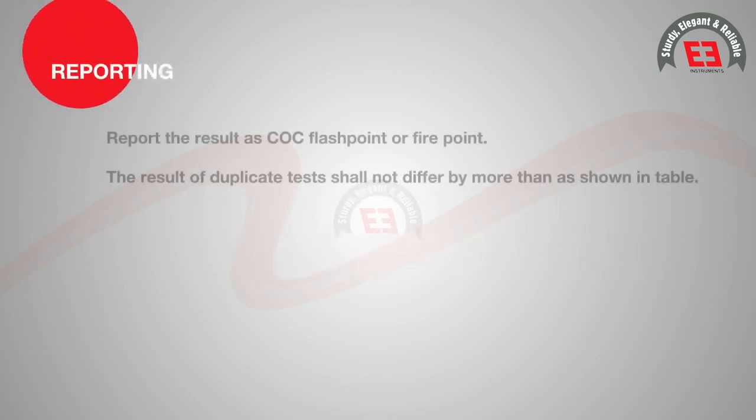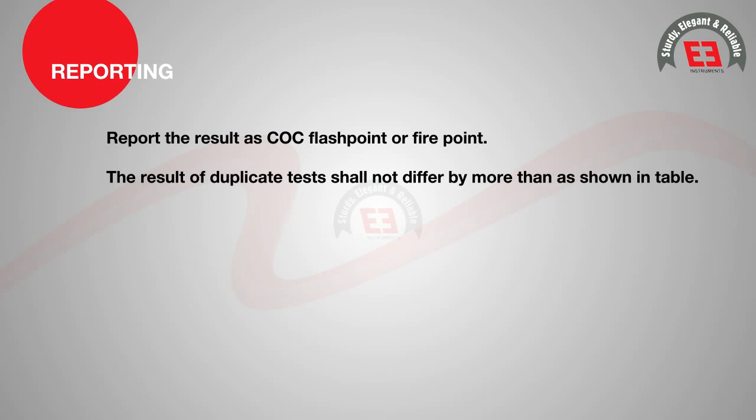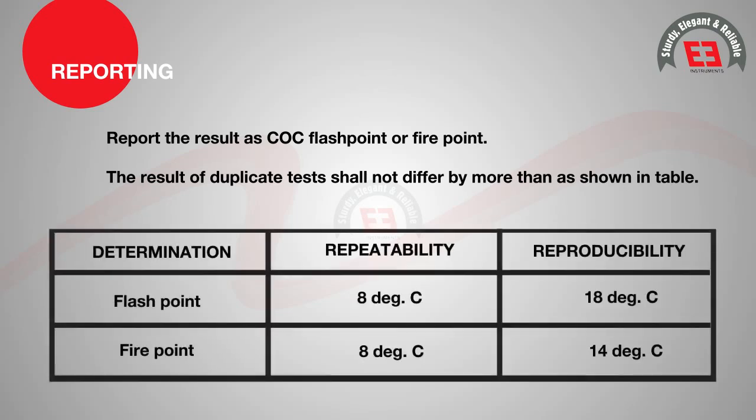Reporting. Report the result as COC flash point or fire point. The result of duplicate tests shall not differ by more than as shown in table.